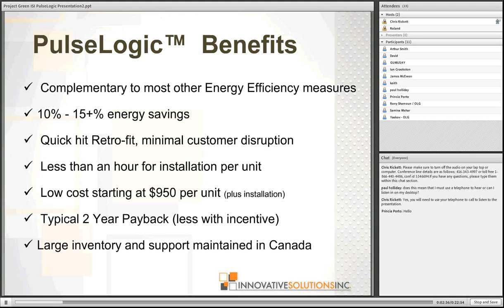The simplest way to describe it is when you see an RTU that's 95% or 90% efficient, they've already done everything they can because you purchased a new RTU. A lot of the rooftop units or older boiler systems have been in place sometimes 10, 15, and 20 years. If there isn't budget to replace them, we'd like to consider ourselves the next best solution. Effectively, what the PulseLogic unit does is it adds the same type of algorithms, or a new set of brains, to an older system, giving it the ability to be more efficient.